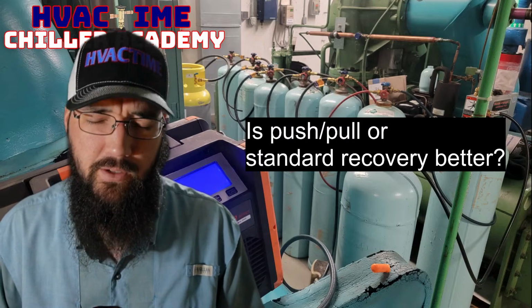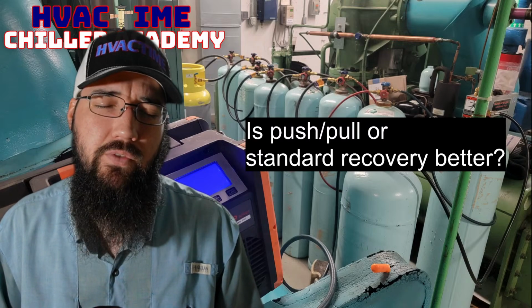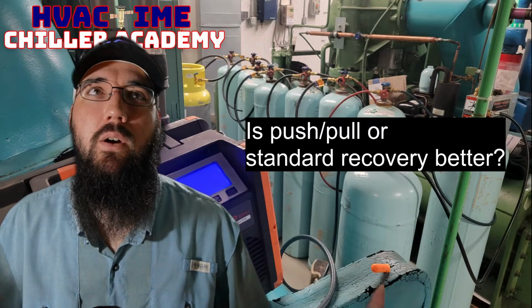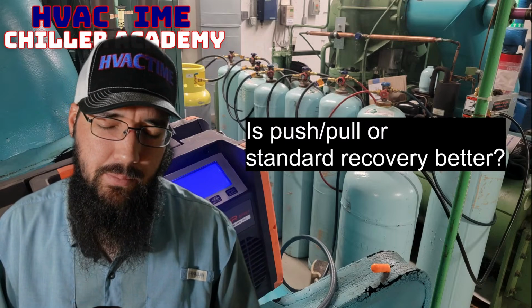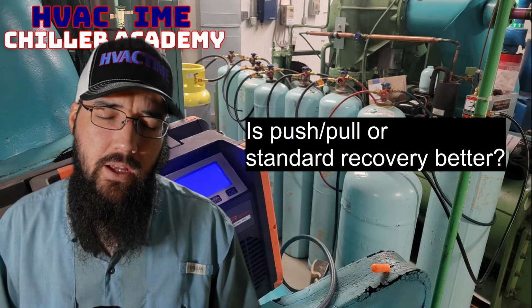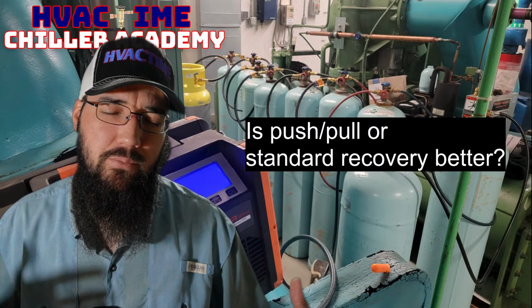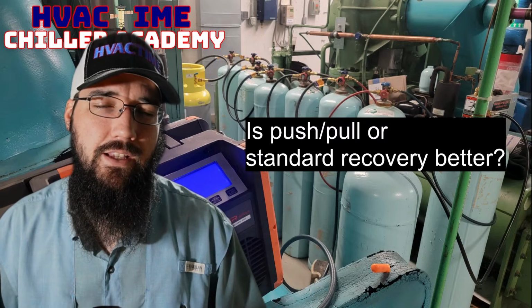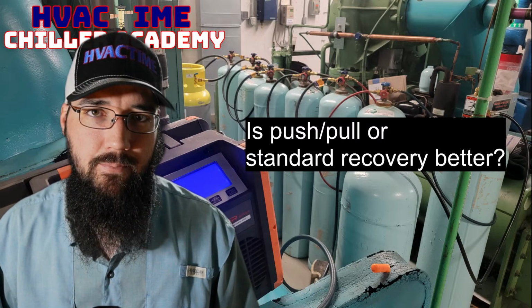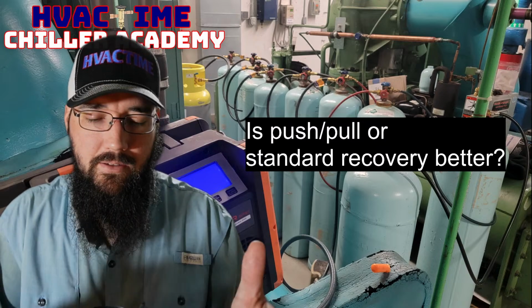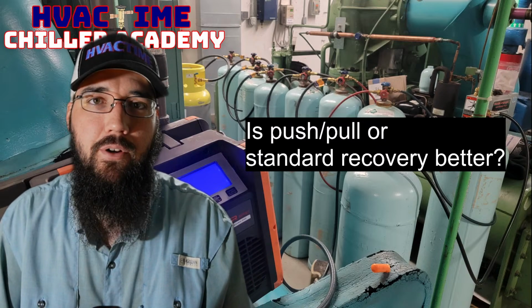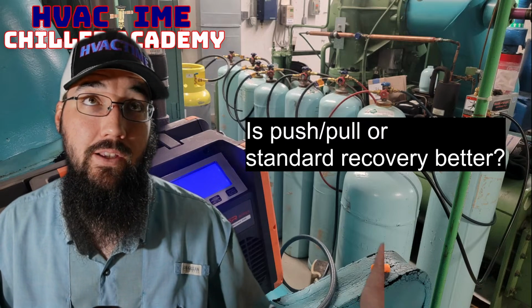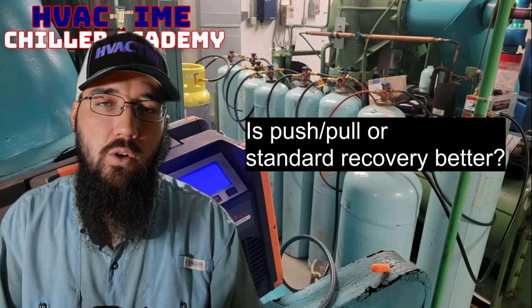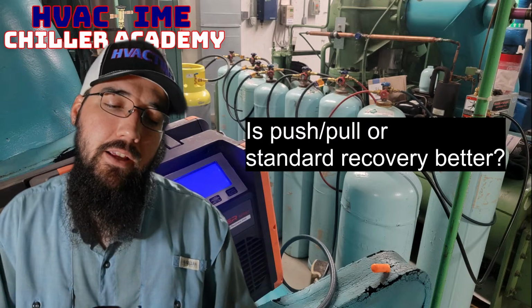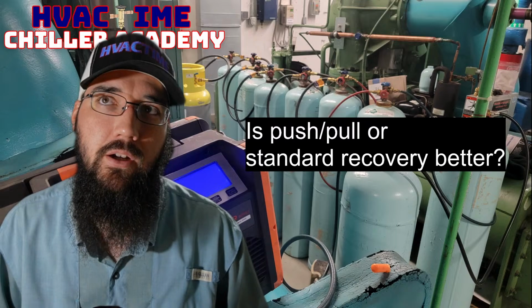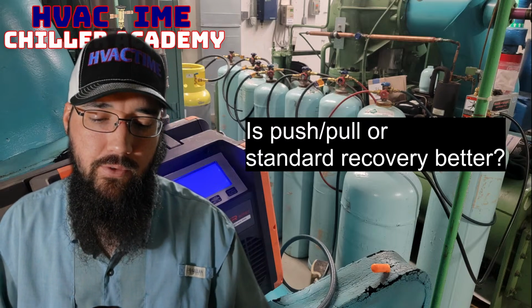A perfect example is a York YVAA, or even a YCIV as far as that goes, but especially the YVAA. The YVAA stacks the majority of its refrigerant in the evaporator at shutdown - it's a perfect flooded evaporator, not even a DX style like the YCIV was. All we need is a port to pull from, but they give us this little dinky quarter-inch port down by the filter dryer where the eductor is.